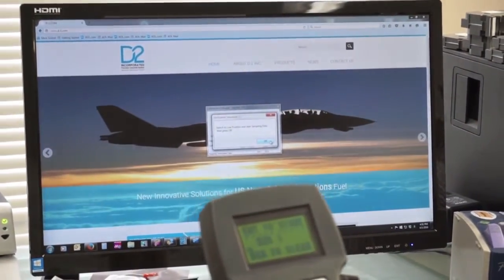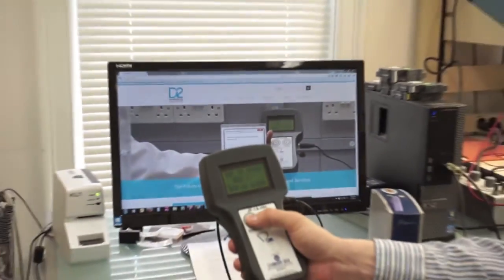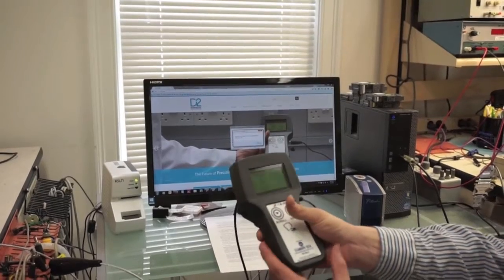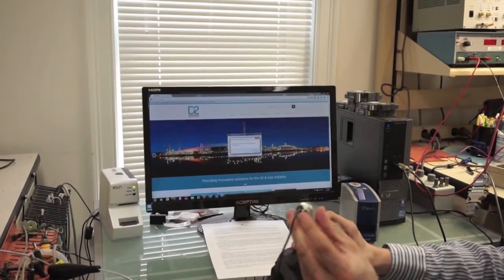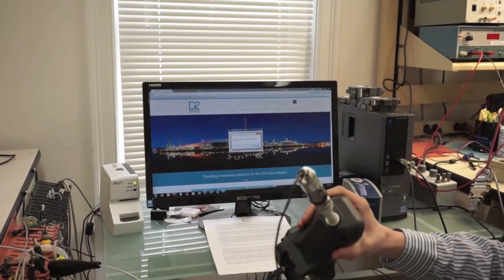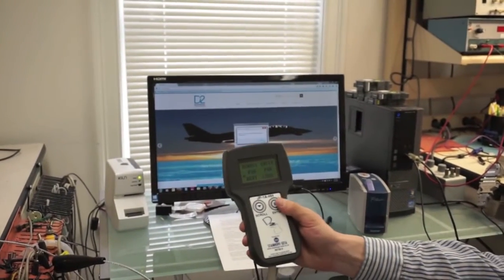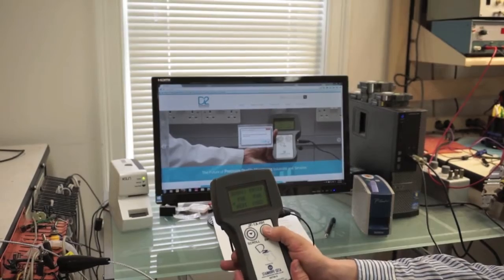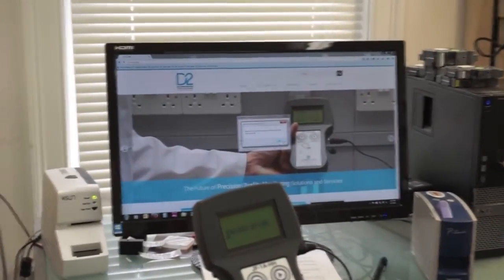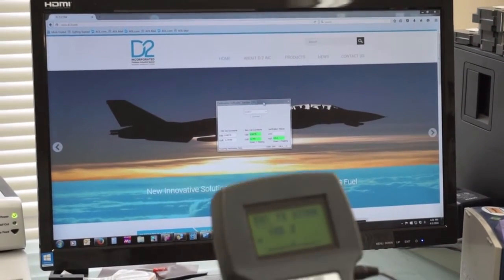It says, switch to low position and start sampling data, then press OK. So you hit scroll to clear the screen. You put the unit into the low value position on the verification tip. You hit enter for location 0. Once it's calculating, you hit OK on the screen. And you wait for it to finish until you get a notification on the screen.